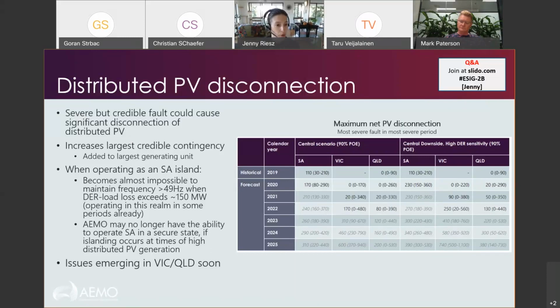But we're already in the realm where, when we're operating South Australia, particularly as an island, we have potential to see 100 megawatts or more of PV disconnecting. And that means that in some periods it's almost impossible to maintain frequency above 49 hertz for those kinds of contingency sizes. And that means that we no longer have the ability to operate that South Australian island in a secure state if that islanding occurs at a time of high distributed PV generation. Now, that's an unlikely coincidence of things, but it can happen. And so it's very important that we prepare to be able to manage the system. And we've got work underway to do that.